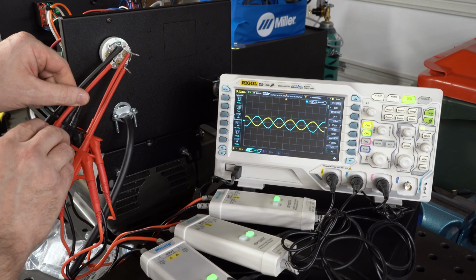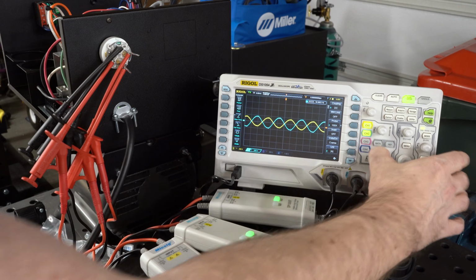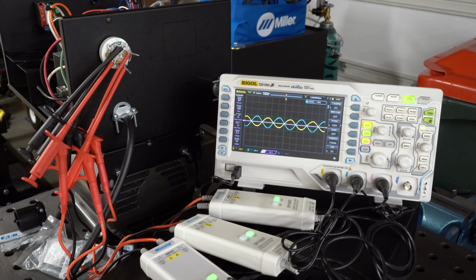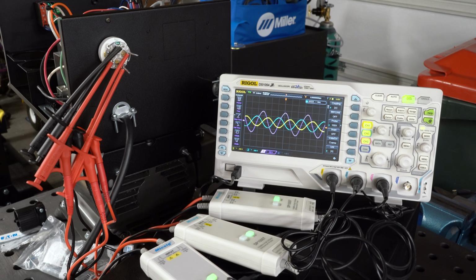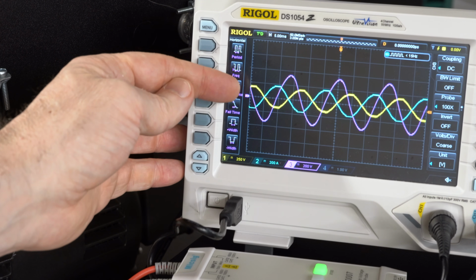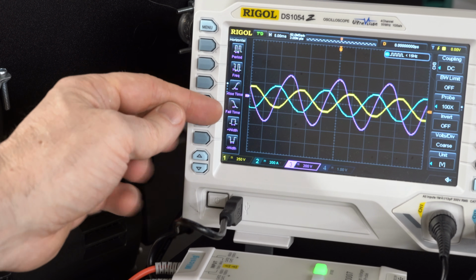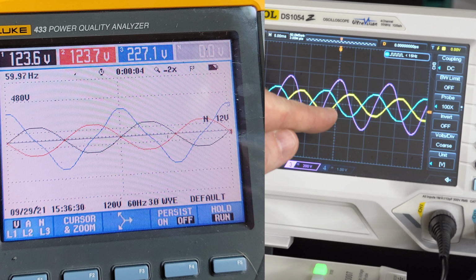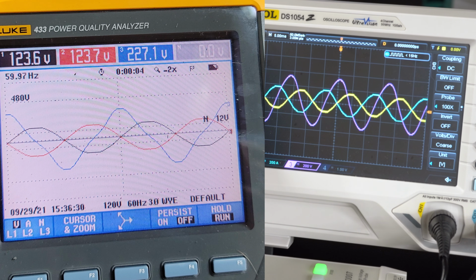We go ahead and put a probe on the wild leg and start the phase converter, we see exactly what we expect. We've got the two 120 volt phases with respect to neutral and the 208 volt wild leg 90 degrees between them. This is, of course, exactly what we saw on the power quality analyzer photos. Thank you, Jason, for sending those in.